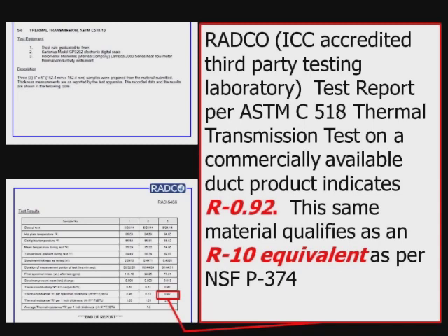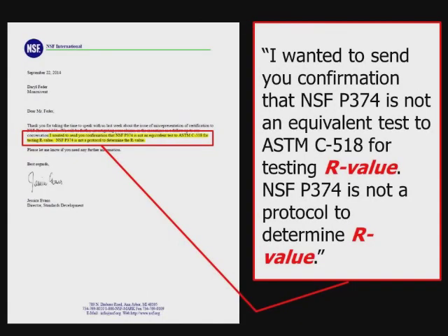So moving on, and as actually a good segue into my last statement there, we did have correspondence with NSF, and we directly asked the question. And Miss Jessica Evans, who is the Director of Standards Development for NSF, her statement to us was that the P374 test is not an equivalent to the ASTM C-518 for testing R value and is not a protocol that should be used to determine R value. Plain and simple, straight to the point, right from the horse's mouth.